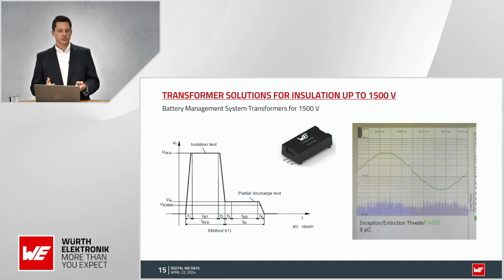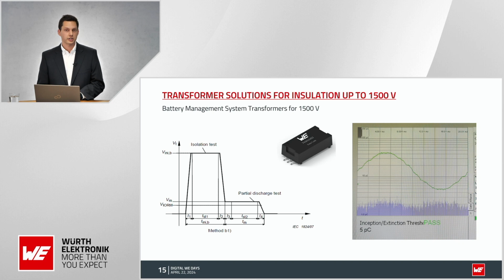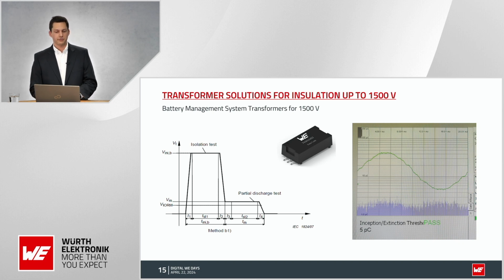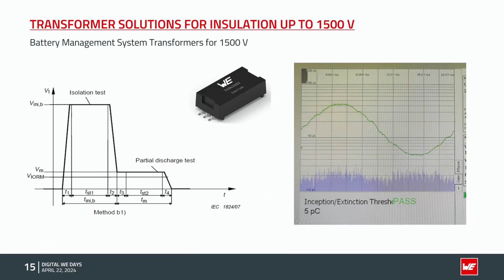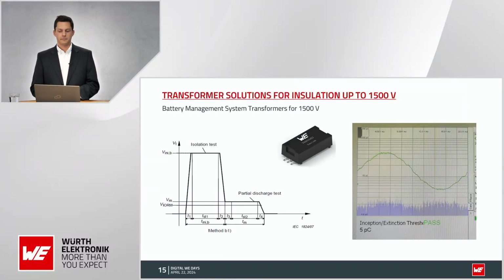A partial discharge test for signal transformers is a test that aims to measure the partial discharges which may occur in the transformer's isolation structure during the test. Partial discharges are electrical arcs that form surges between electrodes of any areas of the isolation media of a transformer between the conductors. These discharges may occur in air bubbles left in the isolation media, gaps in the solid materials, or at the surface of 2 different isolators.